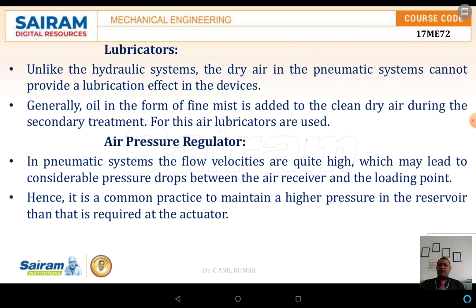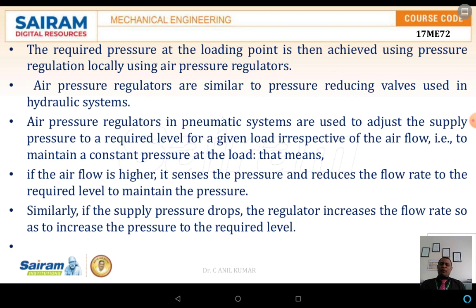The air pressure regulators are a basic necessary element in the line. In the pneumatic system, the flow velocity is quite high, which may lead to a considerable pressure drop between the air receiver and the loading point. Hence, the common practice is to maintain high pressure in the reservoir than that required at the actuators. If there is any pressure drop at the actuators, it is compensated by flowing excess air from the reservoir. For that reason, air regulators are required between the DCV valves and the actuators, or before the DCV valves. The required pressure at the loading point is then achieved using a pressure regulator locally.